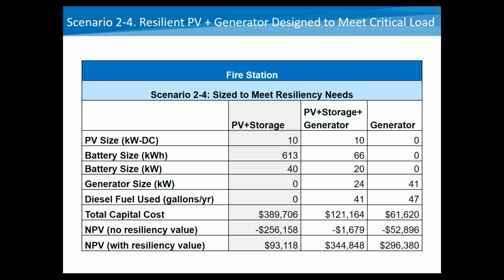In this case, we again have that maximum 10-kilowatt PV system, the maximum number that can fit on the roof, in the PV and storage column. And we have a very large battery, a 613 kilowatt hour, 40 kilowatt battery system. The reason there's such a large battery in this case is that the PV system is really pretty undersized compared to the load. So the battery basically has to fully charge up before the outage, and then it just continually discharges during the outage. And that battery is providing most of the energy during the outage because the PV just can't provide all of the energy that's required.